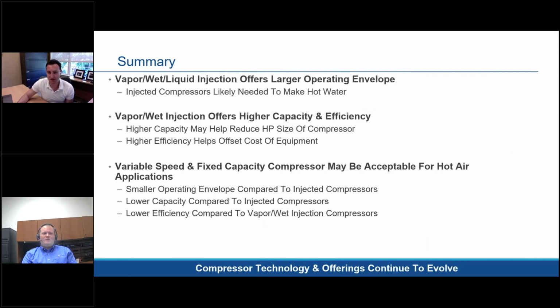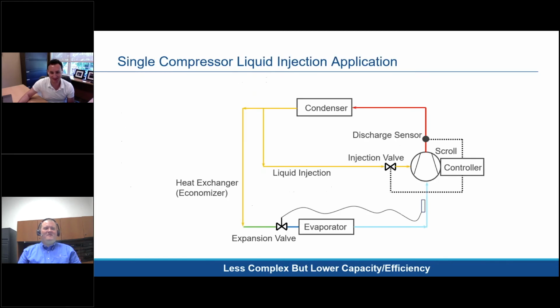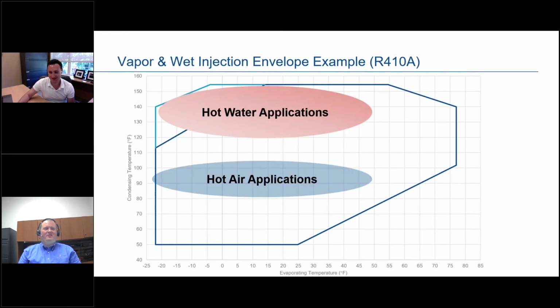Otto, I got a couple more questions. One is, what is the highest temperature hot water that a compressor can generate fairly efficiently? That's a general one, you could leave it to the end if you want. I think a lot of that depends on what they mean by fairly efficient. Hot water, like I said earlier, a lot of it depends on the system itself and what your outside temperature is. If your outside temperature is 10 degrees, most OEMs can probably make 150-degree hot water out of 10-degree ambient temperature, because that's going to operate typically at 0 degrees evap, 150 condensing.